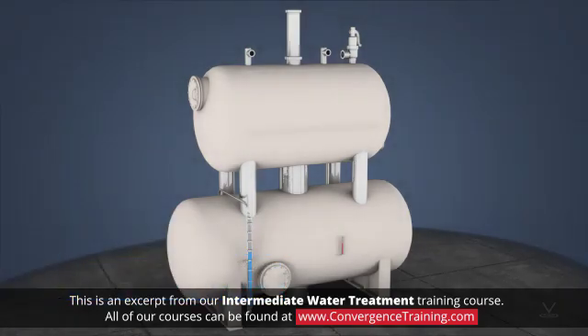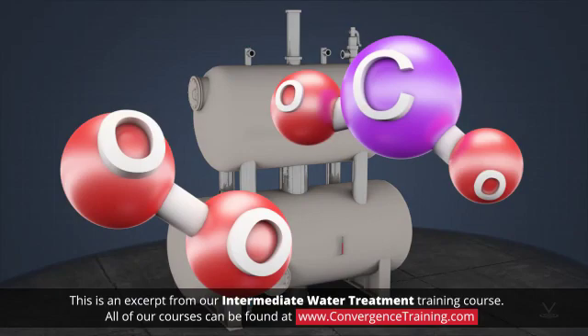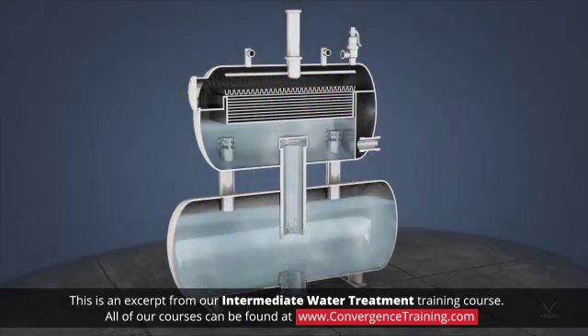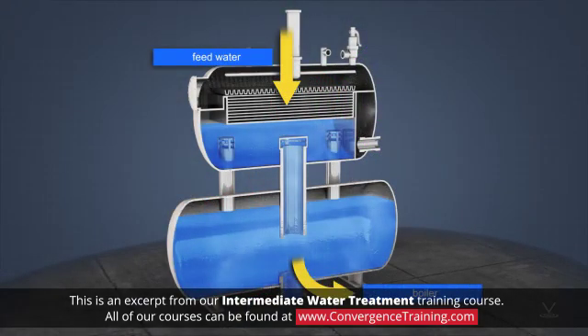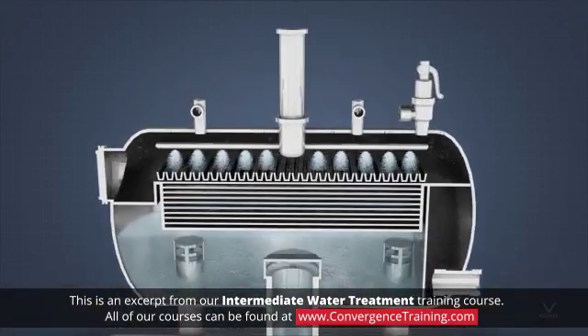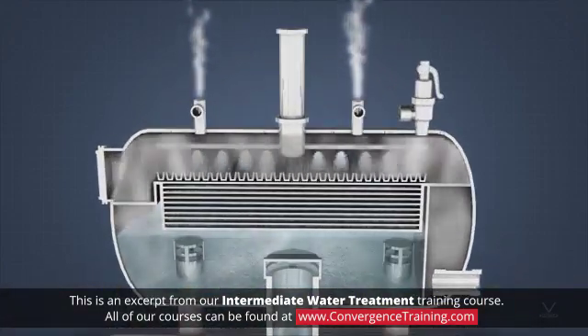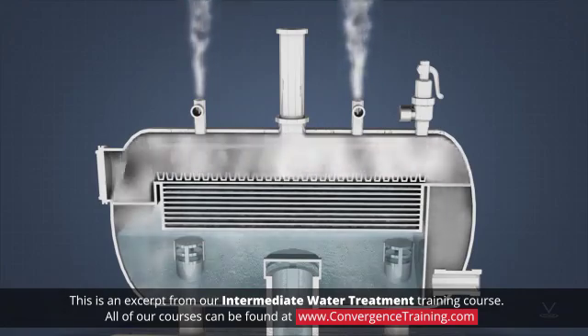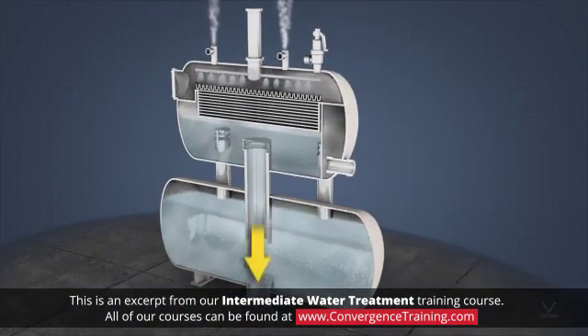After pretreatment, corrosive gases such as oxygen and carbon dioxide must still be removed from feed water to a boiler. Mechanical deaeration can remove these gases, especially oxygen, reducing them either to an acceptable level for the boiler system or to a suitable level for application of oxygen scavengers.